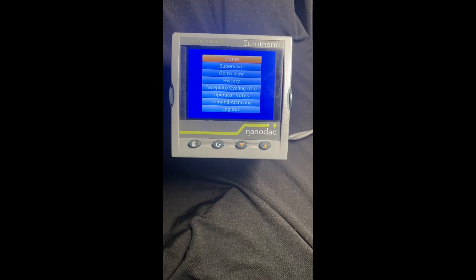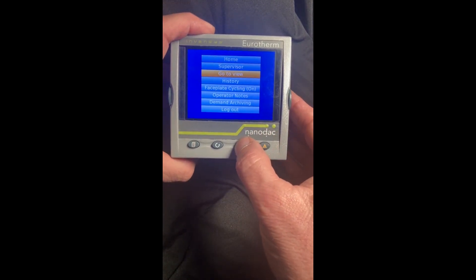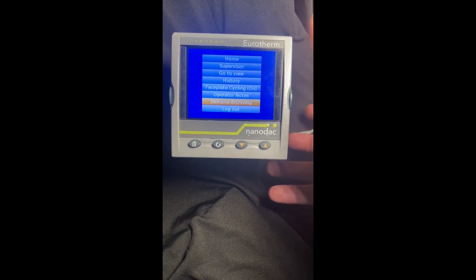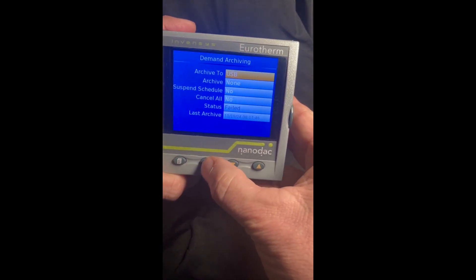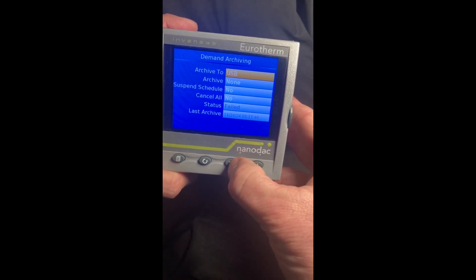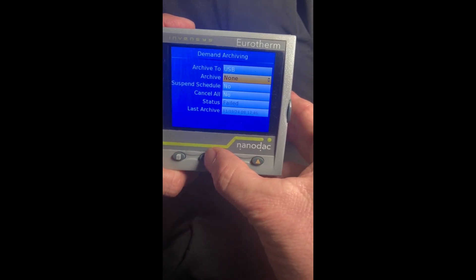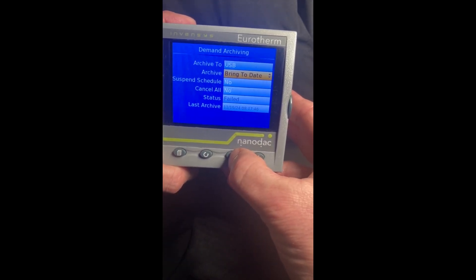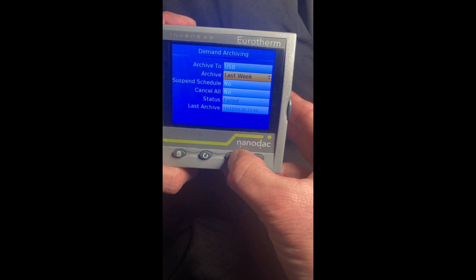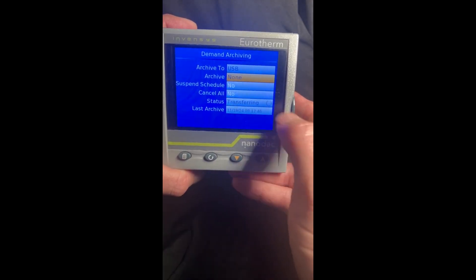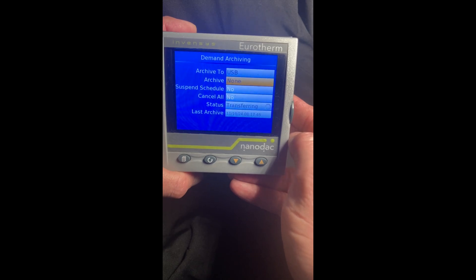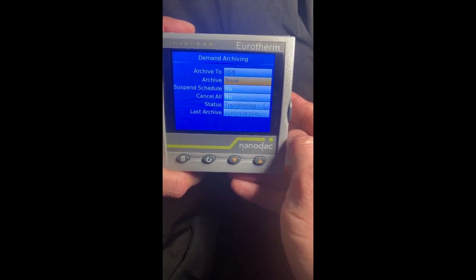Now in supervisor mode, the demand archive shows up but the controller is still controlling the process. We can plug in the USB again, hit demand archive, go to archive to USB, hit enter, and we'll do the last hour again. The transfer is now underway — we'll let that finish up.